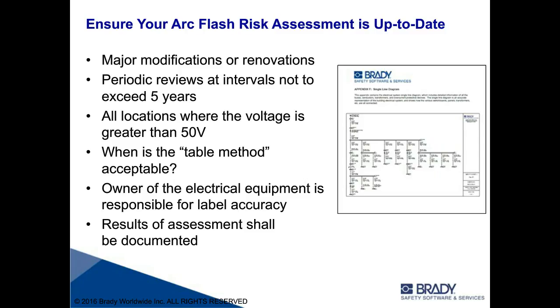Another question I often get is, when is the table method acceptable? Do I have to have an engineer come in and do this work, or can we use the tables in NFPA 70E to define what the risk levels are? The authors of 70E make it very clear that their intent was to encourage the use of the engineering analysis method over the table method, but they do allow for the use of these tables, with parameters that have to be met in order to use them.